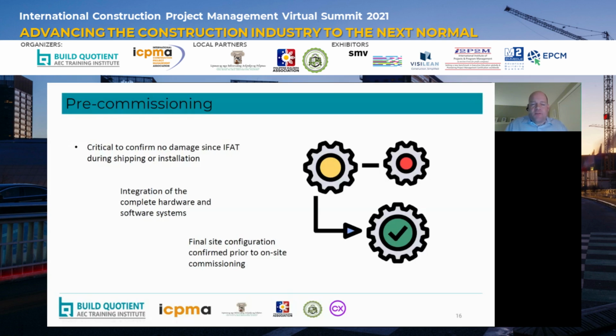This differs from IFAT in that now we have everything that was installed during the IFAT testing, as well as all the peripheral cables and all of the end devices. So we have full fidelity of the system, and we can now test all aspects of the system in its permanently final installed configuration. The pre-commissioning phase is essentially to confirm that we've got our installation back intact from what we had in IFAT, plus all the final configuration.